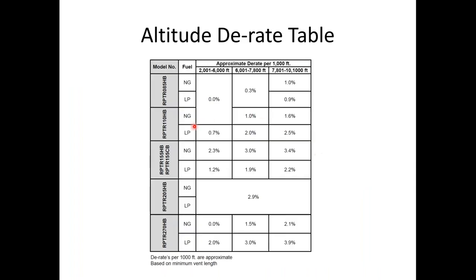And our derate for the products, 1% per thousand feet. The 270 is going to be almost 4% per thousand feet for the derations. When you do derate with the control, and I'll show you what you're doing with the control, it will automatically give you its new BTU firing rate. And we're going to go through a video showing the altitude adjustments on the control.